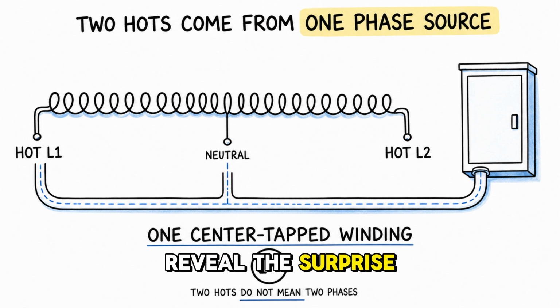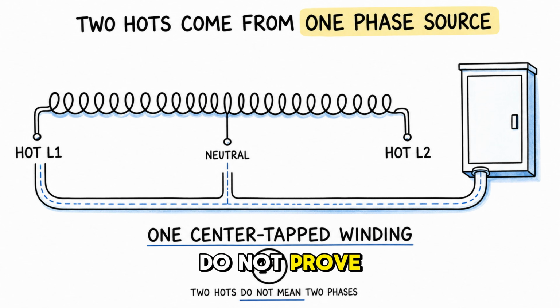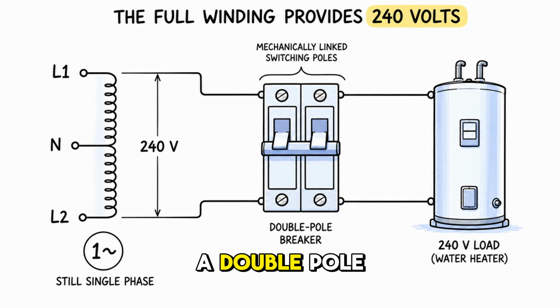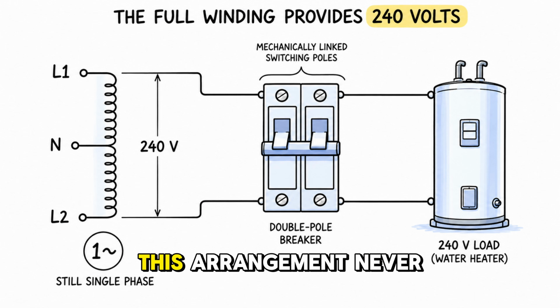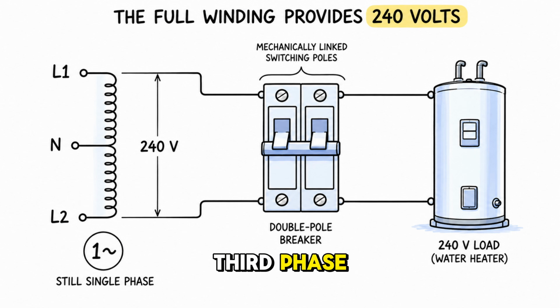Now we can reveal the surprise inside an ordinary home panel. Its two hot wires do not prove that it receives two-phase power. They are simply the two ends of one center-tapped transformer winding. A double pole breaker connects a load across those ends, allowing the full winding to provide 240 volts. This arrangement never creates a second or third phase.